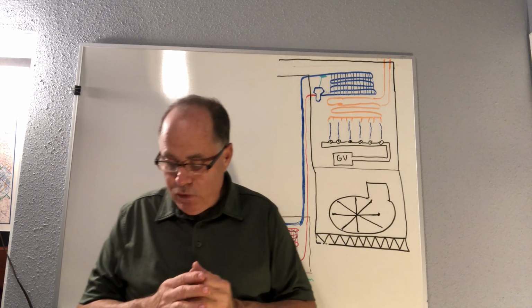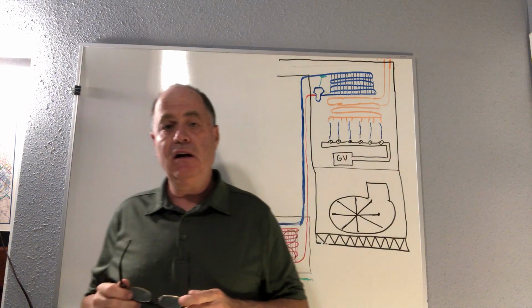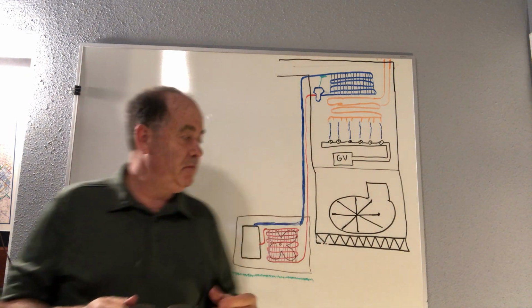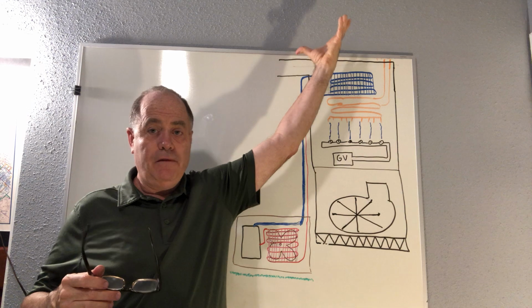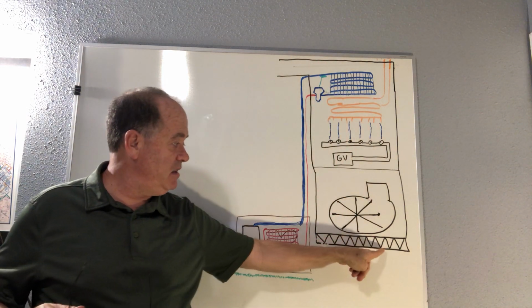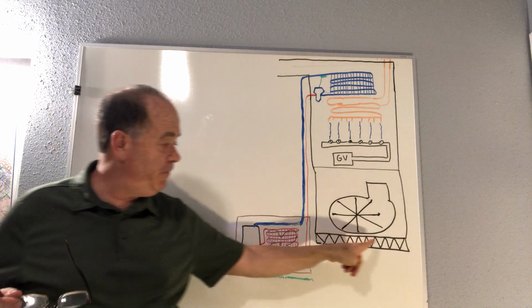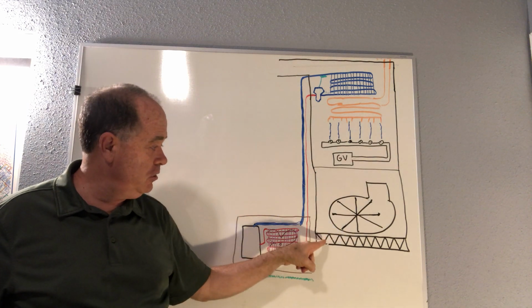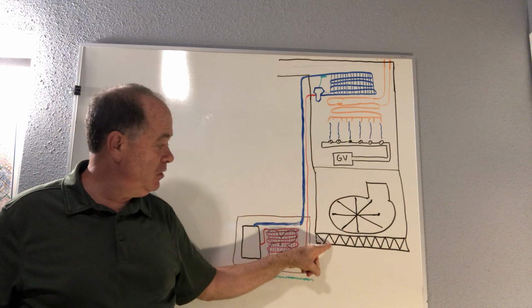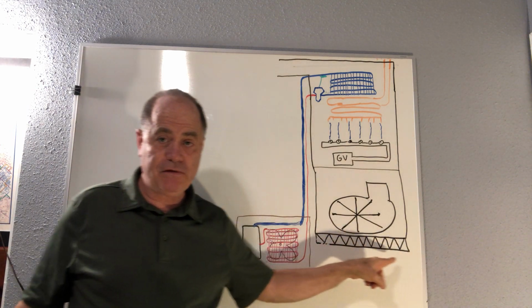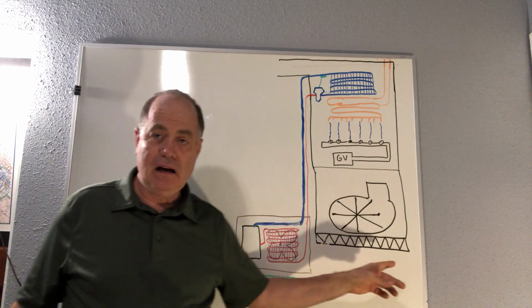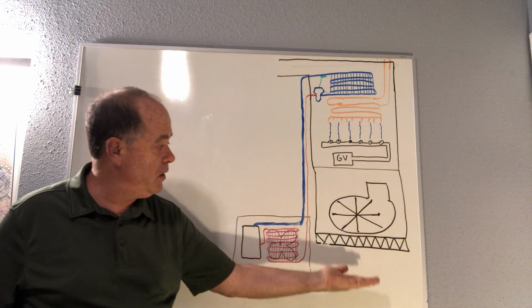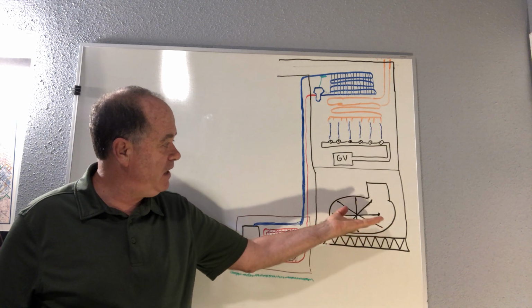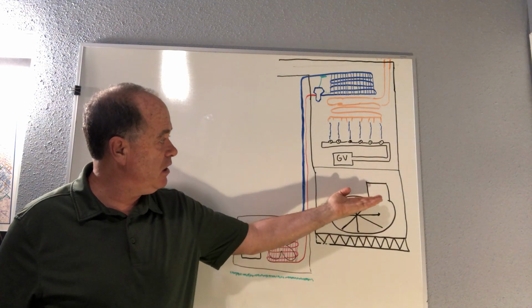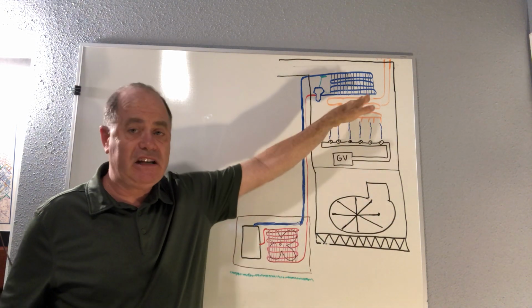All right, we have different types of forced air furnaces. Here we have an upflow furnace where the air comes in the bottom, and this right here is the air filter, and this is actually the official symbol for air filter on blueprints from ASHRAE. Okay, so the air is sucked in the bottom, and then the fan pulls through, filters the air, and then blows it up over a heat exchanger.